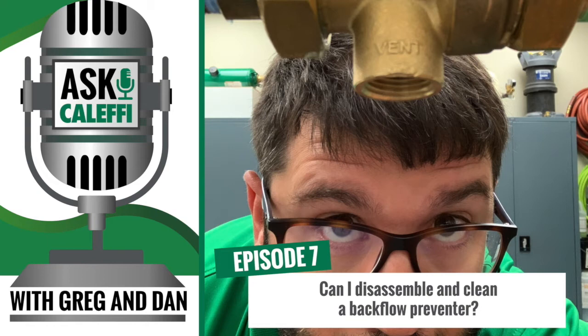In reality, these checks aren't opening and closing all the time. They're opening when water is added to the system and then closing. If you get a water hammer or a surge, that's when it can knock some debris loose and that debris will get stuck in those checks and it won't reseal. Those checks will actually float a little bit, and when they float, that allows a little inrush of water on the high pressure side to come in. When they go to settle back, that's when that piece of debris gets wedged in there.